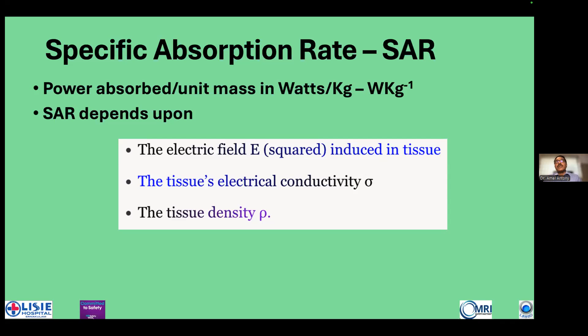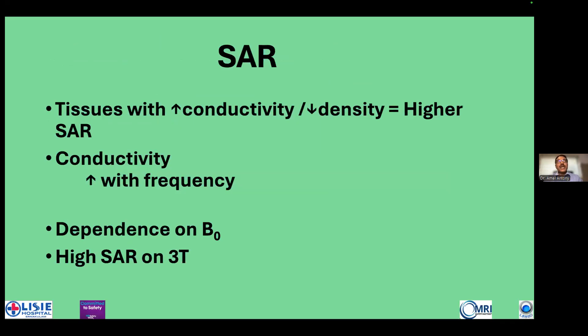Now, tissues with increasing conductivity and reduced density will have higher SAR, and conductivity, we know, increases with frequency. And remember, between 1.5 and 3 Tesla, definitely the specific absorption rate is higher on a 3T.